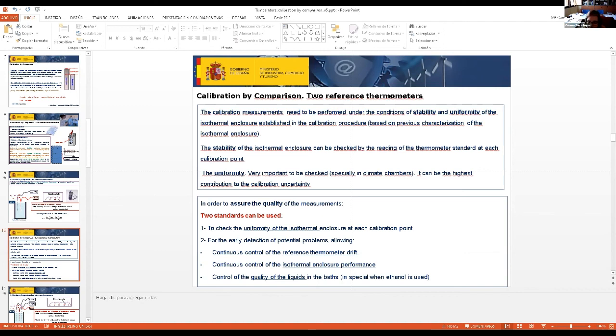Why is it important to use two thermometers? Well, the first point is that with two thermometers, we will check the uniformity of the isothermal enclosure at its calibration point. I mean, we will check not only that the stability inside the isothermal enclosure is stable enough, but that the difference of temperature between the two points where the thermometer and the standard are is also small enough for our uncertainties.